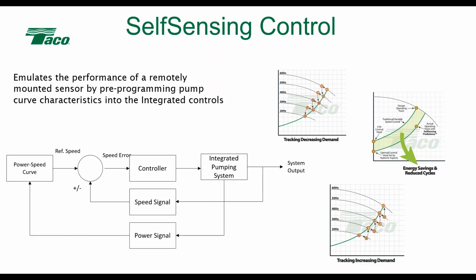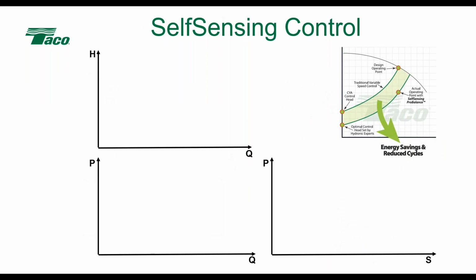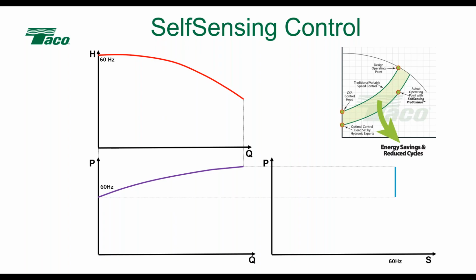So what we have to understand is, as the system is operating and as the flow rate demands are changing, as valves open and close in the system, and we change the flow rate, the power demand changes. So as we start to close valves, the power demand required by the pump starts to decrease, and so we know we're not operating on the curve where we're supposed to be. This slide has several builds to it. So we have our frequency curve, or our power and speed curves, and we know that as we move back and forth on the pump curve, we have a resultant power that goes with it, okay?